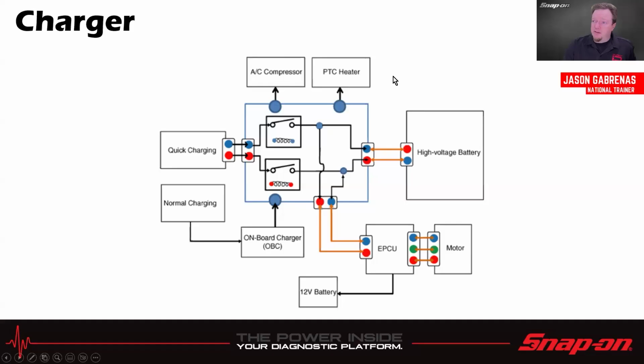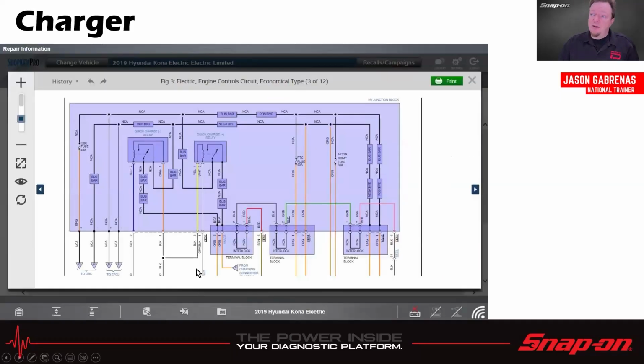Heater and compressor. One thing to note, I don't think I mentioned it in the slides, is your HVAC system is going to run off the battery. So your AC compressor is usually going to be high voltage electric, and then the PTC heater would be electric as well. Here's just an example of what the high voltage junction block would look like. We've got a couple different relays in there. There's your terminal block, your interlock, a bunch of different terminal blocks, so those can be removed, I guess. And then we have the quick charge relays, which, when it's in quick charge mode, would just click over and allow that voltage to flow right into the battery. A couple bus bars, positive and negative, and so on in that module.